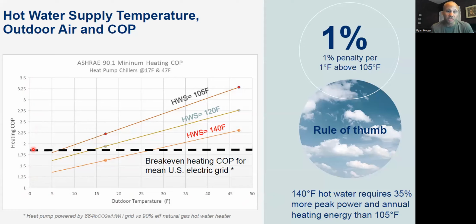COP, coefficient of performance, like we said before, like 3.5 is 350% efficient, right? This dotted line here is what many people will utilize as kind of like the coefficient of performance that I need for this to kind of make some sense for the amount of energy it takes to distribute electrical power to my building, right? And you saw that on the small split systems, we had a 5-degree COP of 1.75 was considered a cold climate heat pump. This is at 1.8 on here, but same kind of logic. If I can get above that line, I'm usually in pretty good shape, right? So 105-degree design temp for my hot water loop would crush it. It'd be awesome all the time, right?